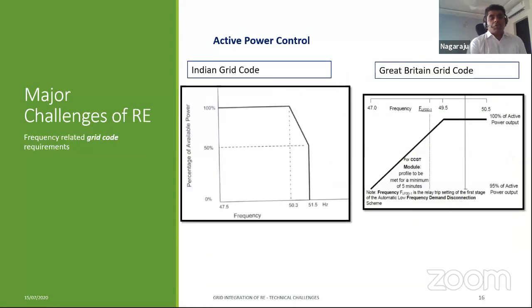Then active power control. So we just talked about the inertia part, then active power control. On the left-hand side, I'm showing you the grid code. You look at the green part, here is the grid code requirement. So what are the grids looking for? The left side picture is the Indian grid code. You see that the Indian grid code requires the renewable generation to provide constant output across a frequency range of 47.5 to 50.3 Hertz. And output should not fall below 50% for frequencies up to 51.5 Hertz. For conventional plants, it's easy, but for renewables, it's challenging.